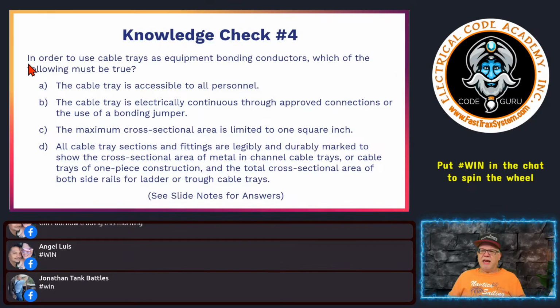Okay, let's check our knowledge really quickly and see what we got here. In order to use a cable tray as an equipment bonding conductor, which of the following must be true? So this one says to use a cable tray as an equipment bonding conductor. All right, it says, the cable tray is accessible to all personnel. It says a cable tray is electrically continuous through approved connections, use of bonding jumpers. Okay.